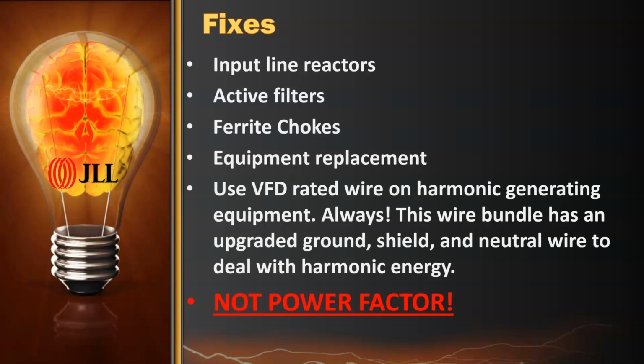The only thing that I would say is, when you put them in the panel, you have to label the panel and say there's a ferrite choke in here, and it's to deal with harmonics. That's to prevent people from opening the panel up at some point and removing it because they don't understand what it is. I would recommend, on equipment, especially new construction, and if you're doing a retrofit, if you're going to install a VFD, use VFD rated wire. It's just something you need to do.